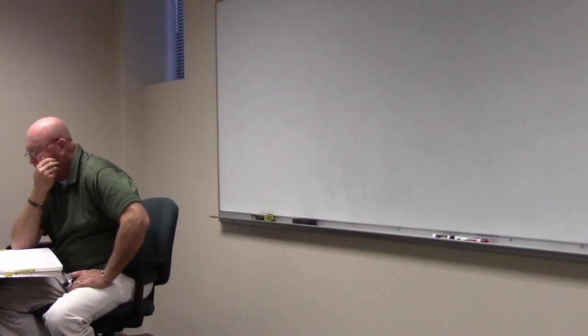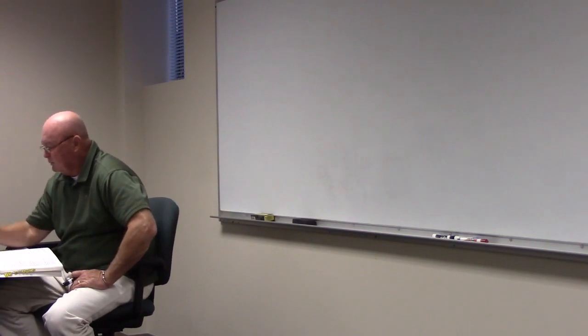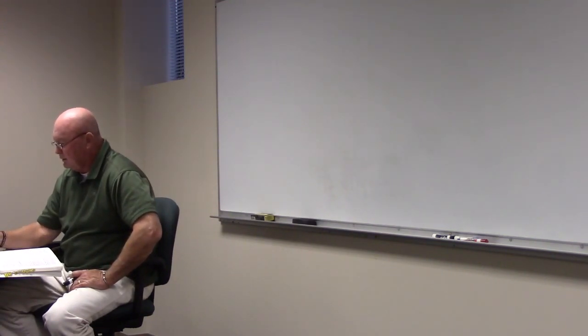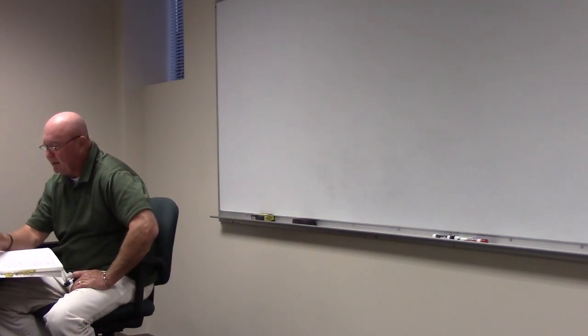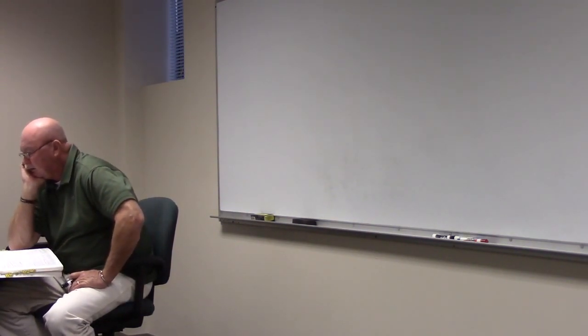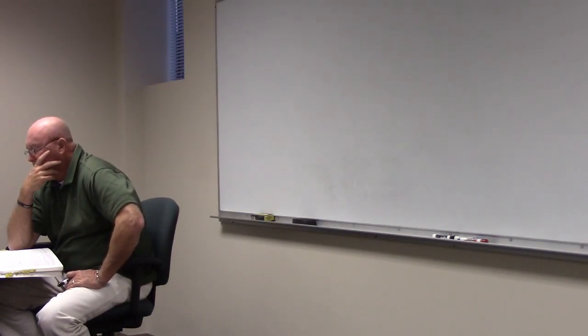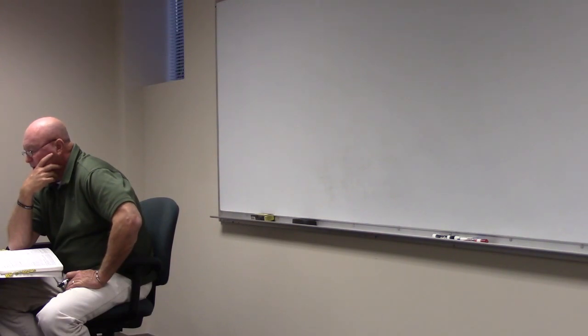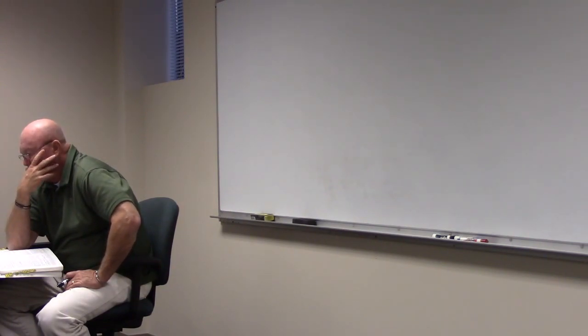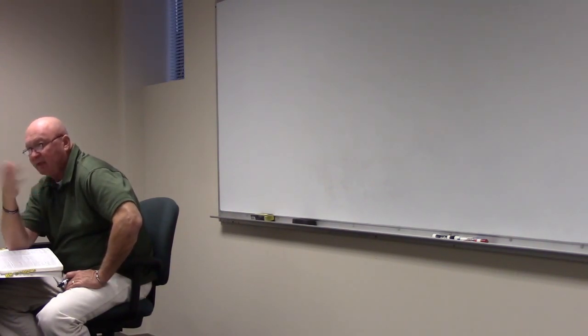All right. Figure 6, which we'd turn over, is a blank form. I'm not going to look at that in much depth right now. We'll come back to that in a minute. Let's just take a look at the first 3 steps to start with. So, step number 1, compute the area of the occupancy. The general lighting load, including general receptacles, is determined by finding the area. So we got to find that. How would we find what the area would be?